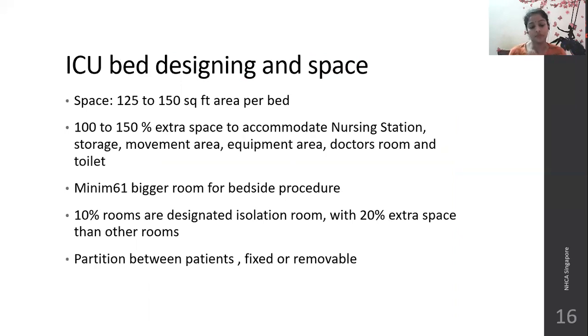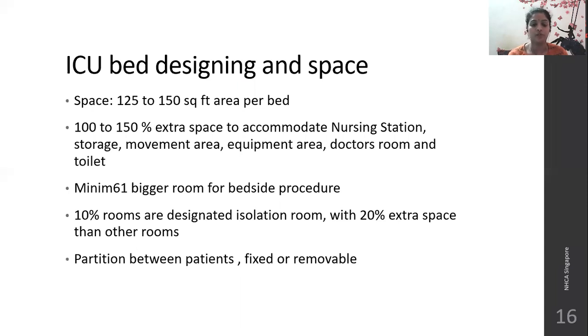For ICU space, it should be 125 to 150 square feet per bed, especially in level 3 hospitals. An additional 100 to 150 percent extra space should be there to accommodate the nursing station, storage, movement area, equipment area, doctor's room, toilet, etc. Minimum one larger room for bedside procedures should be provided. Ten percent of the rooms are designated isolation rooms with 20 percent extra space than the other rooms.